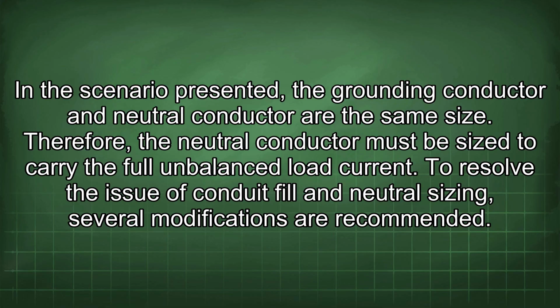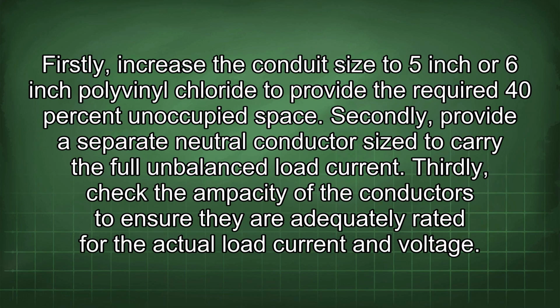To resolve the issue of conduit fill and neutral sizing, several modifications are recommended. Firstly, increase the conduit size to 5-inch or 6-inch polyvinyl chloride to provide the required 40% unoccupied space. Secondly, provide a separate neutral conductor sized to carry the full unbalanced load current. Thirdly, check the ampacity of the conductors to ensure they are adequately rated for the actual load current and voltage.